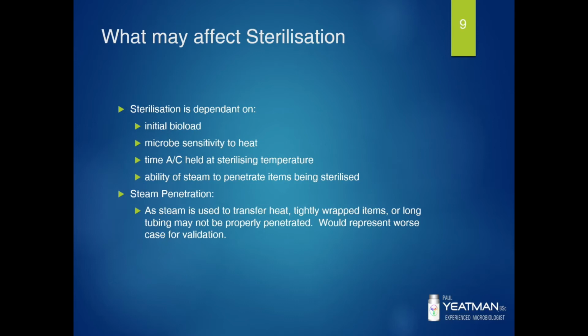So in these cases, the only way you're going to get heat transfer is via radiation, and that's not as effective as moist heat. So there's the difference between, as we talked about on an earlier slide, putting something in an oven versus putting something under steam and pressure. And if you were to identify a worst case situation as part of this, which you do during your validation, then you've got to document it and show that sterilisation is effective here in order to be confident that your entire loading pattern is effective. So if you found that, I don't know, the back left corner of your autoclave was slightly cooler than the rest of it, you'd want to pay particular attention to that when you're doing your validation.